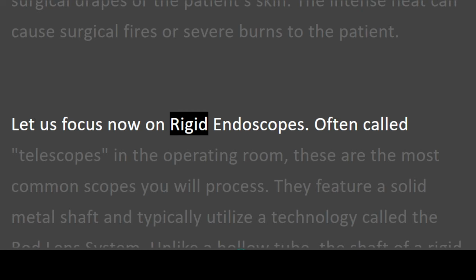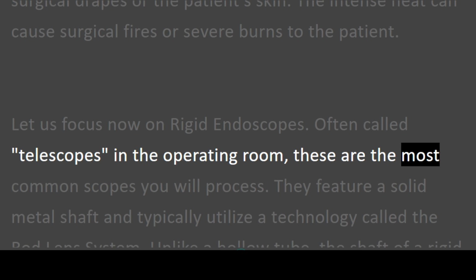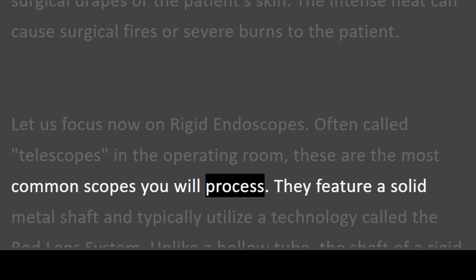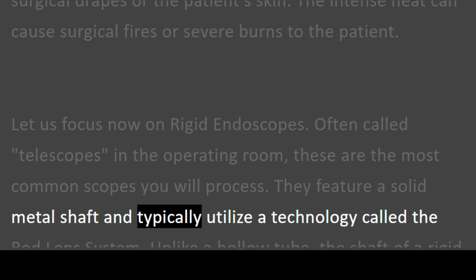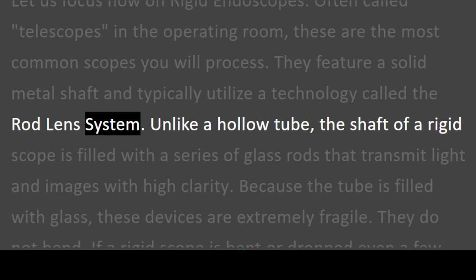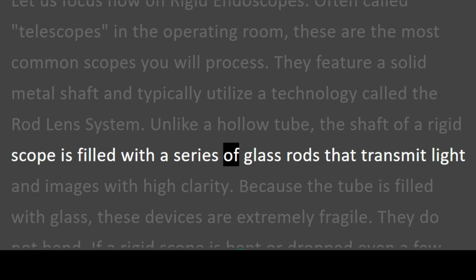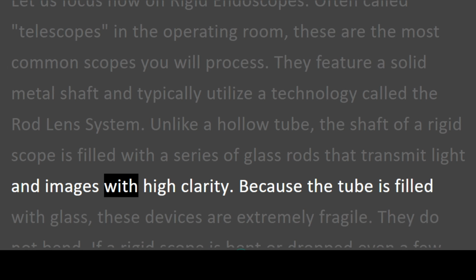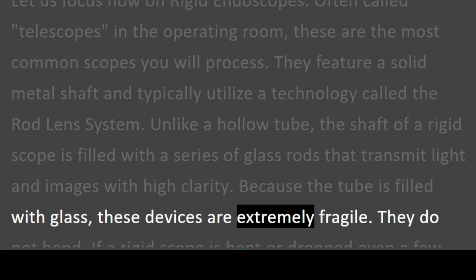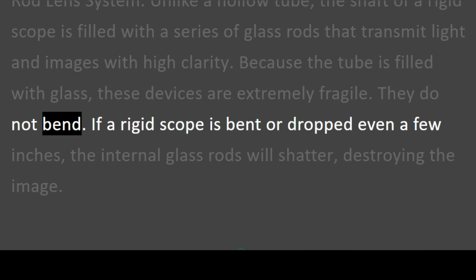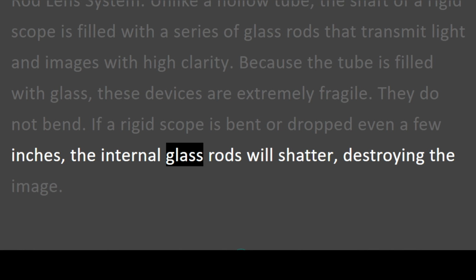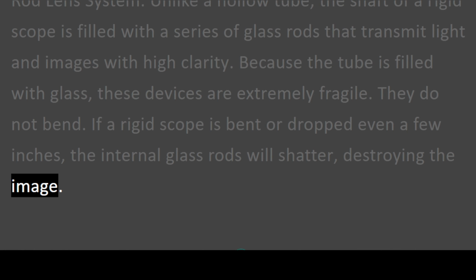Let us focus now on rigid endoscopes. Often called telescopes in the operating room, these are the most common scopes you will process. They feature a solid metal shaft and typically utilize a technology called the rod lens system. Unlike a hollow tube, the shaft of a rigid scope is filled with a series of glass rods that transmit light and images with high clarity. Because the tube is filled with glass, these devices are extremely fragile. They do not bend. If a rigid scope is bent or dropped even a few inches, the internal glass rods will shatter, destroying the image.